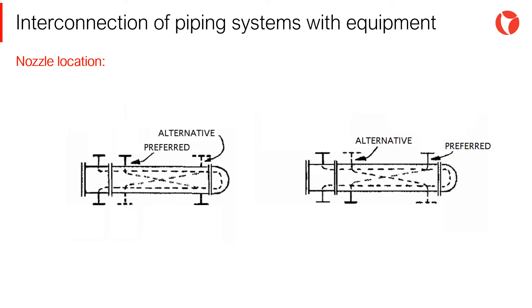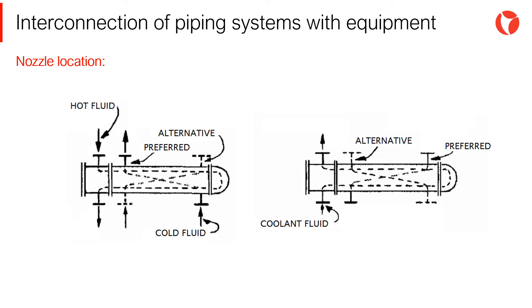The location of nozzles in heat exchangers generally complies with the following rules. The fluid to be heated generally enters the equipment at the bottom and exits at the top, circulating through the shell side or the tube side. The opposite occurs with the fluid to be cooled, which generally enters the equipment from the top, circulating through the tube side or the shell side. Nozzles are arranged so that fluids passing through the exchanger are in countercurrent, so that one fluid is heated from the bottom up and the other fluid cools from the top down.